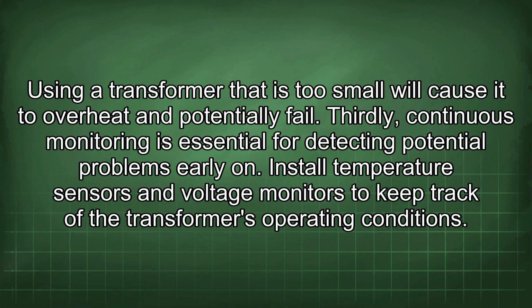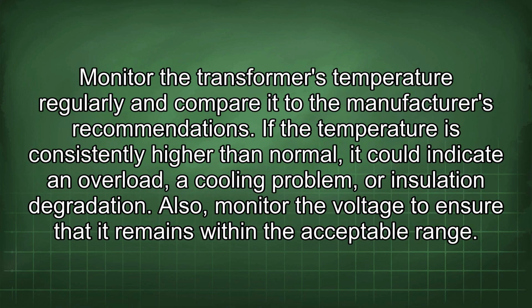Thirdly, continuous monitoring is essential for detecting potential problems early on. Install temperature sensors and voltage monitors to keep track of the transformer's operating conditions. Monitor the transformer's temperature regularly and compare it to the manufacturer's recommendations. If the temperature is consistently higher than normal, it could indicate an overload, a cooling problem, or insulation degradation.